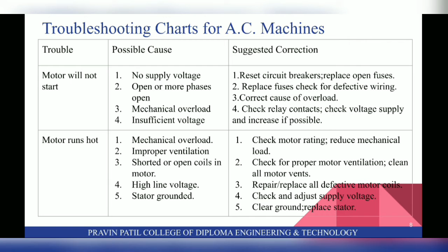Third cause is shorted or open coils in the motor, and the suggested correction for this cause is to repair or replace all defective motor coils. Fourth cause is high line voltage, and the suggested correction is to check and adjust supply voltage. Next cause is stator grounded, and the suggested correction is to clear the ground and replace the stator.